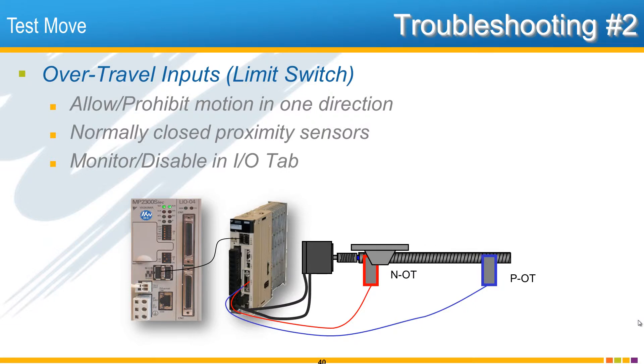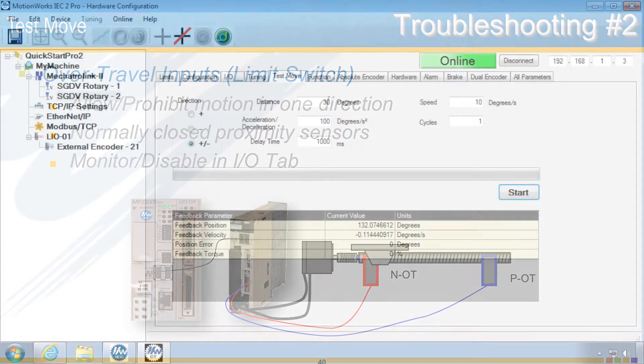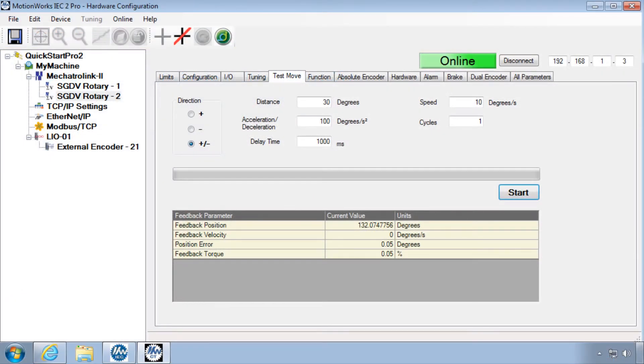Over travel will be indicated on the Sigma 5 front panel as P and N for positive and negative motion prohibited. If you attempt a test move in the prohibited direction, the motor will enable but not move.